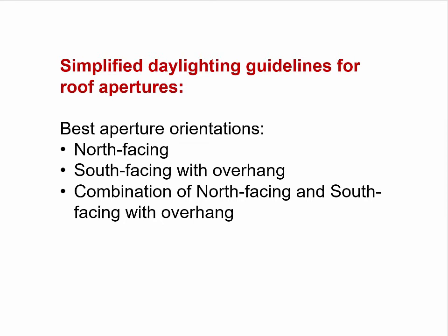We're going to show videos that talk at length about solar behavior, daylight behavior, and various excellent examples of daylighting design. From that we'll come up with simplified daylighting guidelines for roof aperture systems. The best orientations are either north-facing glass — where we can pair photovoltaics on the south-sloping surface to capture beam sunlight — or south-facing glass with an overhang and diffusing elements to intercept beam sunlight and scatter it around the space to minimize glare. The combination of north-facing and south-facing glass with an overhang also works very well.